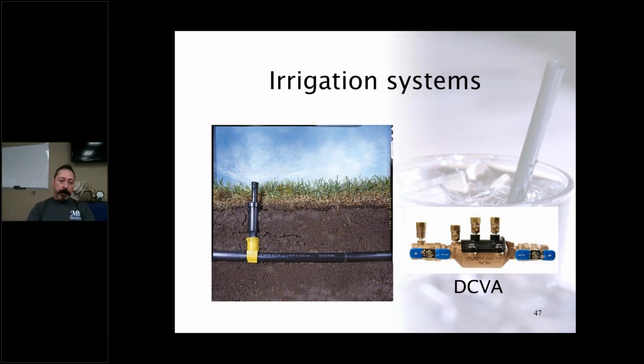Irrigation systems are pretty popular in some areas of the country more than others. Here in the Okanagan, it's dry and hot, so there are lots of irrigation systems. Irrigation systems are not designed to be drip tight, so they are subject to contamination with dirt, nematodes, or residual hard fertilizers. It's not like they're injecting fertilizers, that's agricultural, different. But your standard average household irrigation system, or green space, park, ball diamonds, that sort of thing, can be isolated by something called a double check valve assembly, or a DCVA. There'll be a glossary at the end here, but that's a typical testable device.